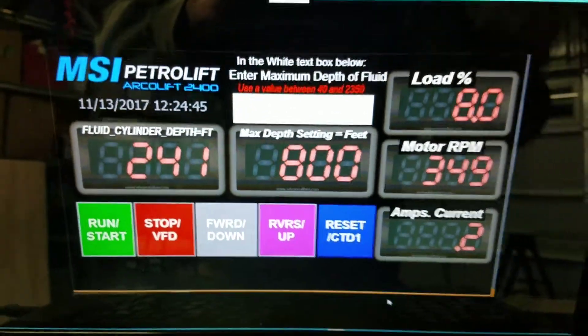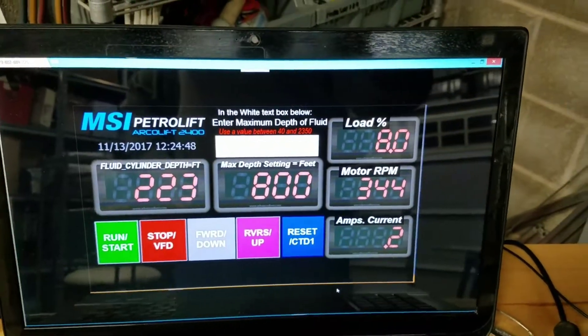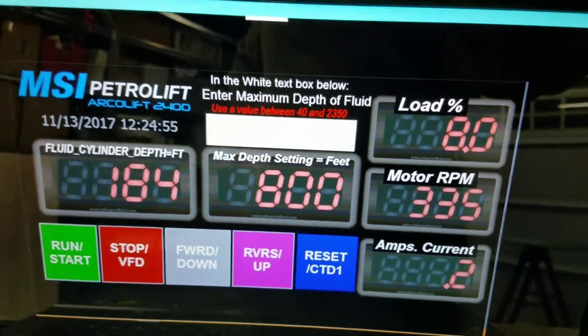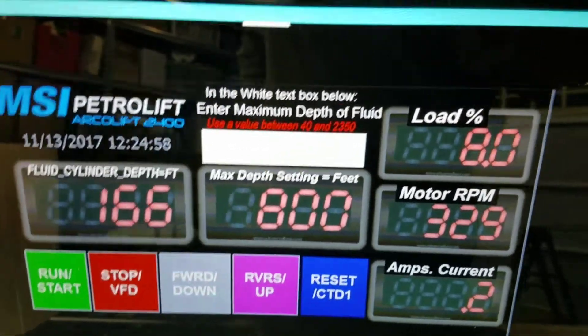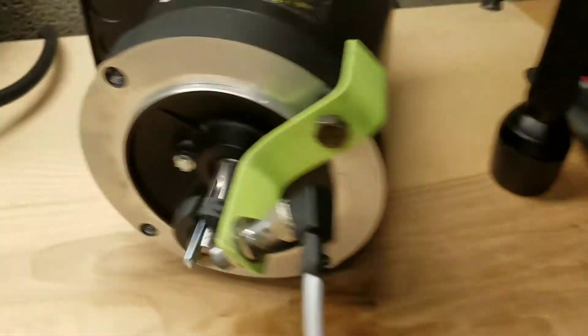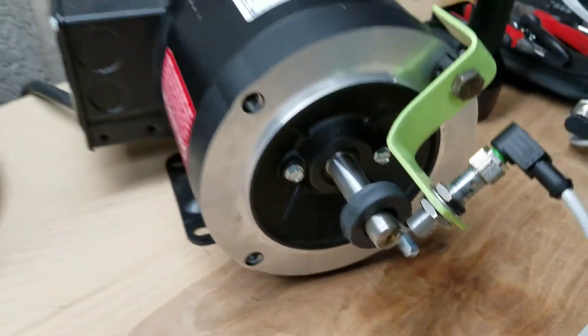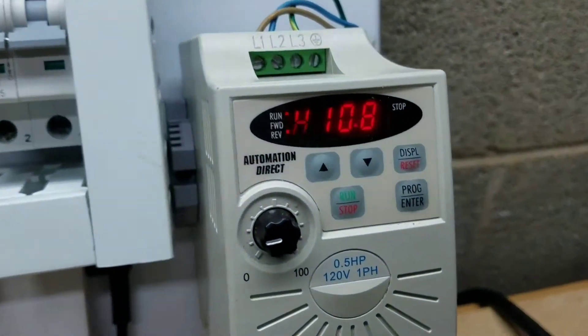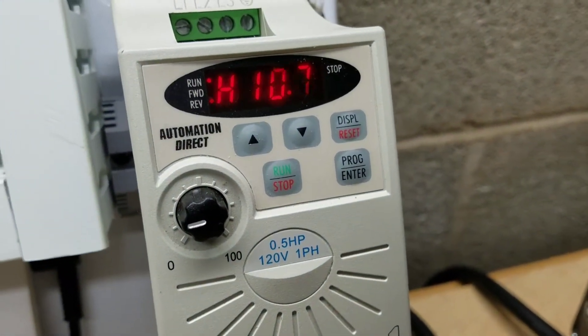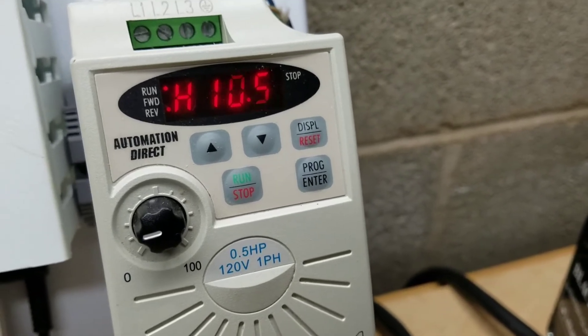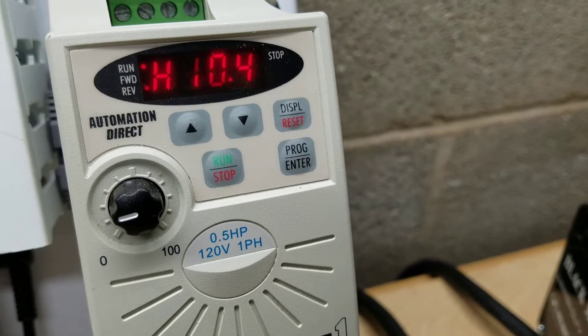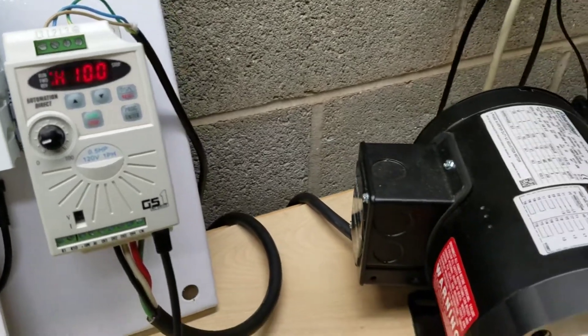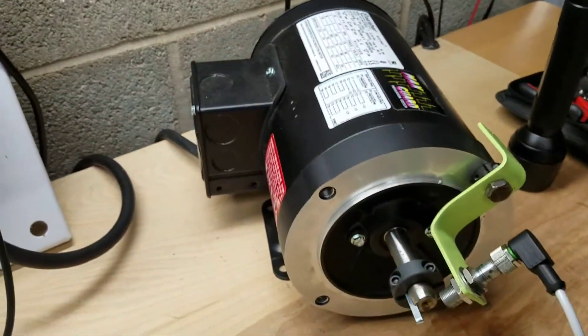The PLC program stops the unit when it reaches zero, then it restarts itself, puts itself back in forward, and descends back down the wellbore in theory. The other thing I have it doing is as it's coming up the wellbore, I'm decreasing the Hertz by 0.1 every 12 counts. You'll see the frequency in Hertz depreciating as we're coming up — this will be a user-set value based on depth.